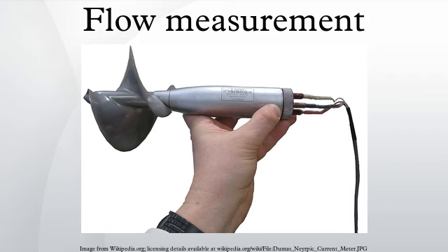The flow direction is generally straight through the meter, allowing for higher flow rates and less pressure loss than displacement-type meters. They are the meter of choice for large commercial users, fire protection, and as master meters for the water distribution system. Strainers are generally required to be installed in front of the meter to protect the measuring element from gravel or other debris that could enter the water distribution system.